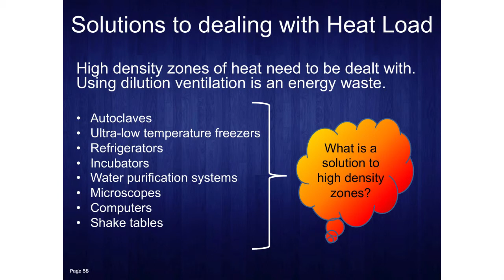One of our solutions has been putting in dedicated exhaust and allowing those spaces to run a little bit higher temperature. So basically in our freezer farms or in our equipment corridors, we want dedicated exhaust grills. And those exhaust grills happen to be a lot of times right where the equipment rejects the heat, so we don't let that migrate into other spaces and then drive our air change rates up. You also see that the wall here for the equipment corridors traps that heat. So we make sure we hold that right up near the ceiling and deal with it before it can migrate into other spaces and cause those spaces to have to absorb that cooling load.